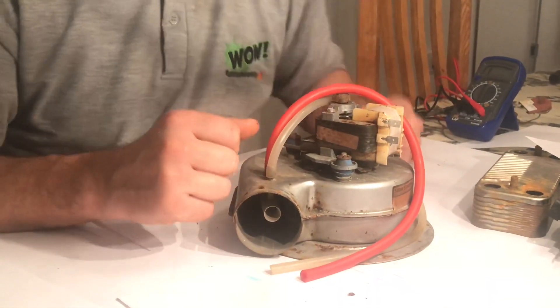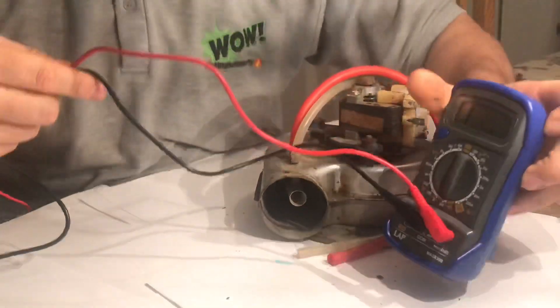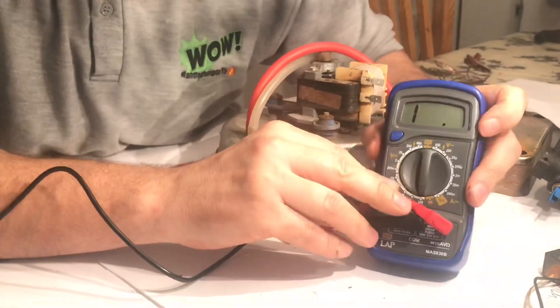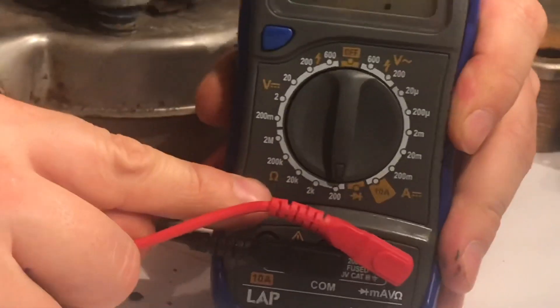A good thing you can do to check an older fan like this is check the resistance. To check the resistance, you get a multimeter and change it to the horseshoe. There's the horseshoe, look.